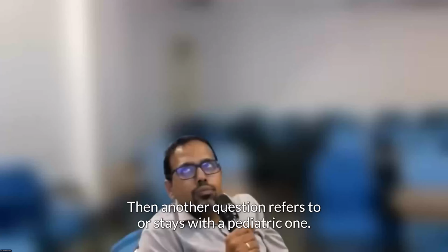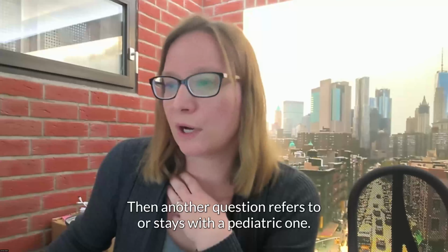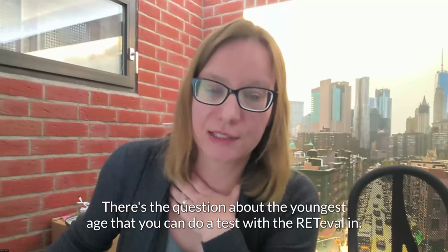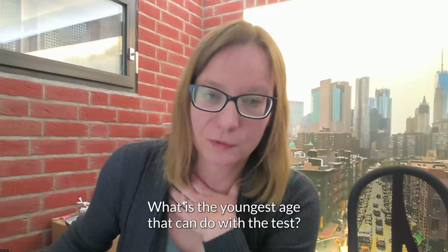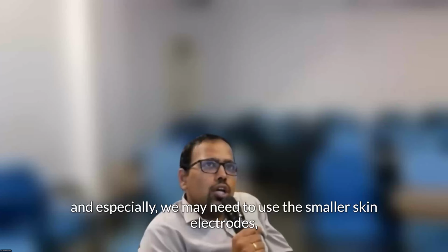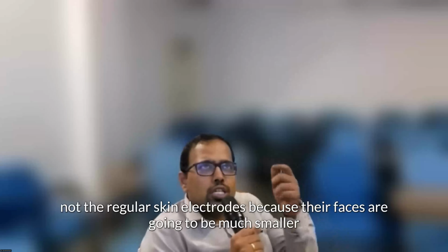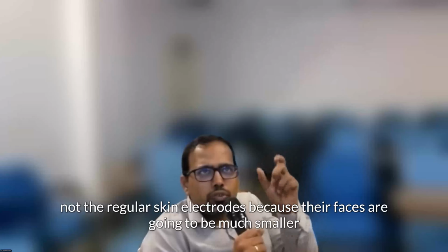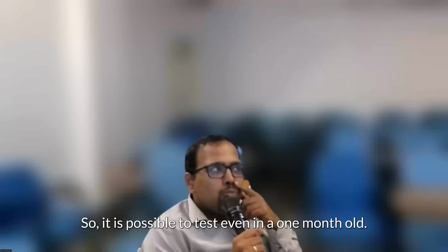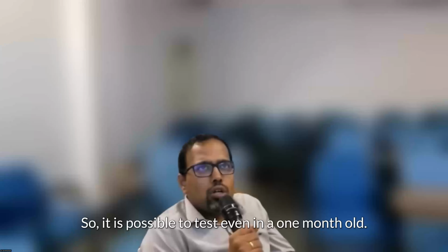Right. Then another question stays with the pediatric one. There's the question about the youngest age that you can do a test with the RETeval. What is the youngest age that you can do the test? As I said, we can test as long as they are cooperative, and especially we may need to use the smaller skin electrodes, not the regular skin electrodes, because their faces are going to be much smaller if they are quite young. So it is possible to test even in a 1 month old.